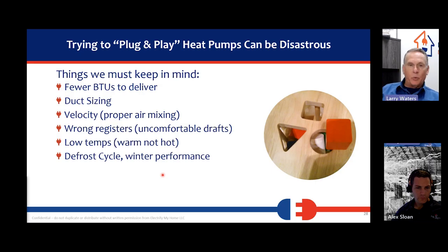We're heating with much lower temperature, so it can feel drafty. Defrost cycle screws up winter performance, and the common solution for this has always been we put a heater strip on here that kicks on during defrost, which is also going to kick on anytime the temperature gets below maybe 39 degrees, because we're going to be slipping and we're not going to be able to keep up. So we're bringing this electric strip heater into play, which is driving up the energy costs in the wintertime. And even if the heat pump can keep up when it gets colder outside, it's going into defrost more often, which is bringing the heater strip on more often. So we have all these problems using all this energy. We can miss all this just by sizing right and using the right equipment.